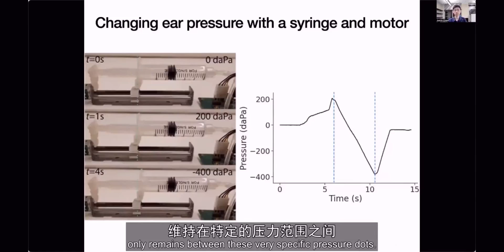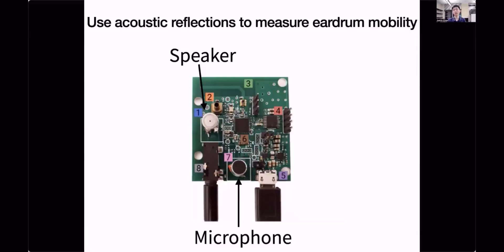Now the syringe is attached, as you can see here, to a stepper motor to move the plunger backwards and forwards very, very carefully at a sub-millimeter precision. And you can perform this pressure sweep very precisely. The motor is then connected through a series of pipes to an ear tip that just goes into the ear, similar to a headphone. And our system is designed with safety in mind. So we have a pressure sensor to make sure that the pressure in the ear only remains between these very specific pressure bands. Now, during the pressure sweep, the attachment also sends an acoustic tone into the ear canal, sends it out through a speaker, and it records what's reflected back using a microphone. And based on how much sound is actually reflected from the eardrum as the pressure changes, you can convert that information into a chart known as a tympanogram that quantifies the mobility of the eardrum.